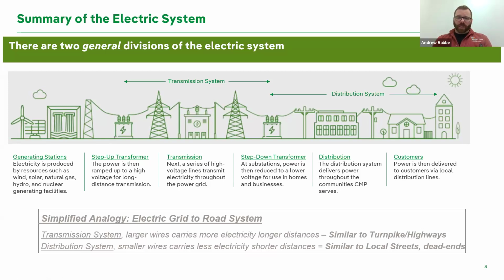Substations are all over the place. Depending on where you are, they might be a single transformer with a single breaker and a single circuit going out, or here in the city of Portland, we have an underground network system where there's 5 circuits and 4 transformers all tied together to feed downtown Portland. So if we lose one circuit due to equipment failure or something, nothing happens - everything else maintains its energization. That's a network system, and there's only one in the state, in the city of Portland.